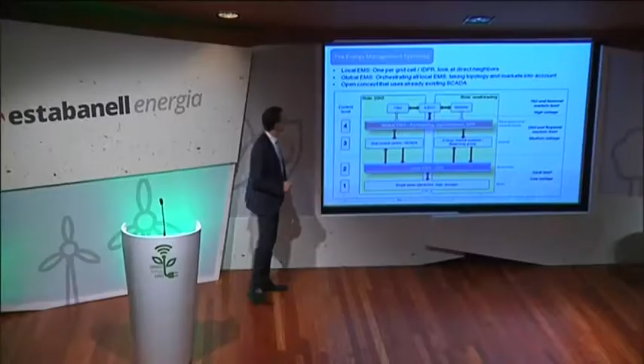What is very important, and I think David asked this morning, is the open structure between the different systems - no level is skipping another one. So it's always a direct communication only with the next level. The set points which come from the global EMS go to the SCADA system, not directly to the local EMS, because there might be security issues or whatever, which is only known here. That's the reason why we can use the SCADA system which was inside directly and integrate it into the system.